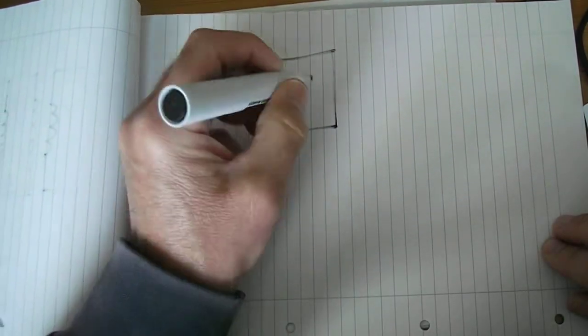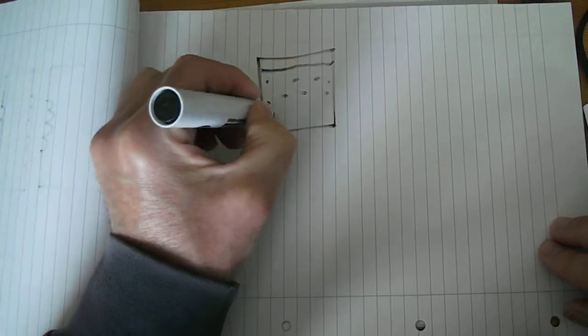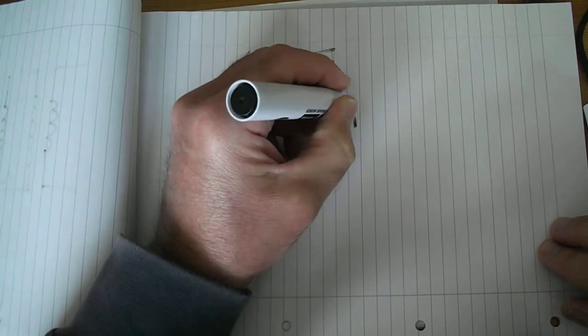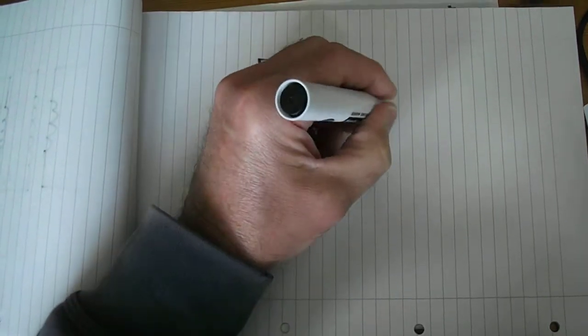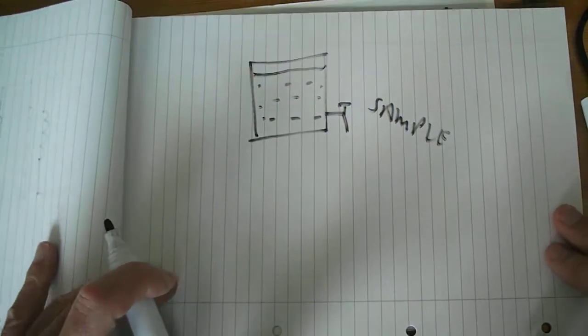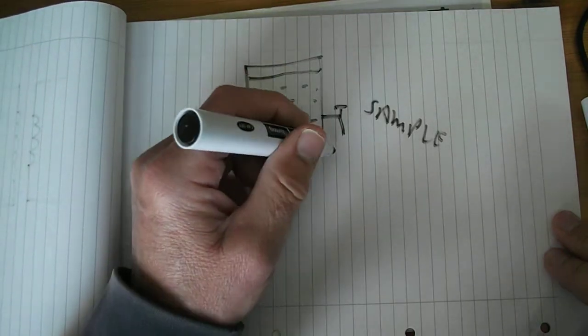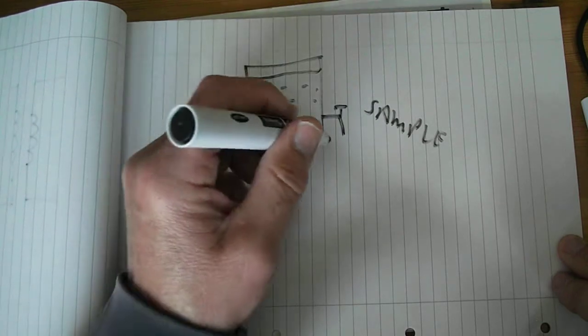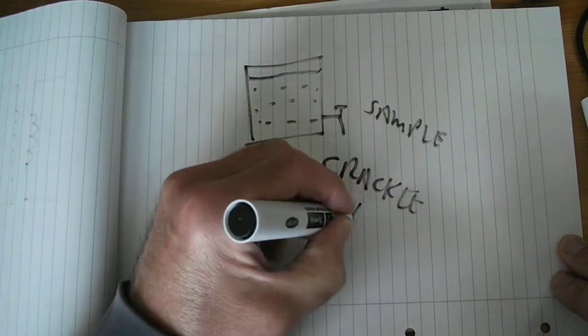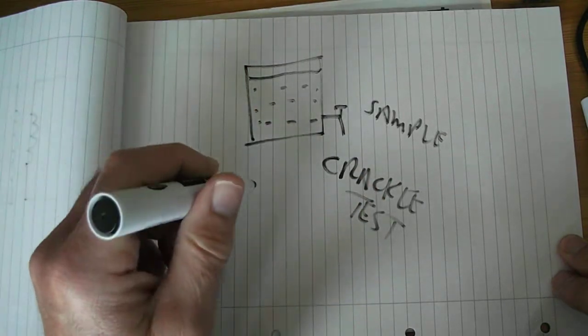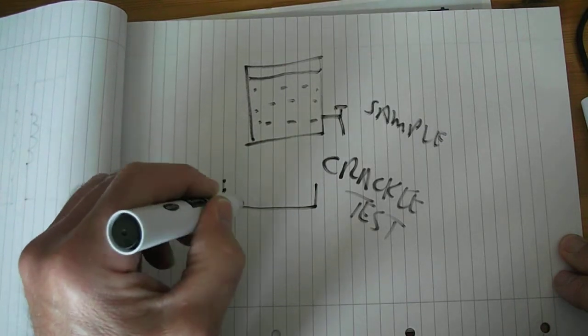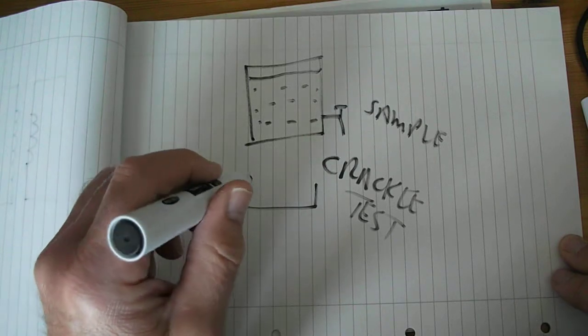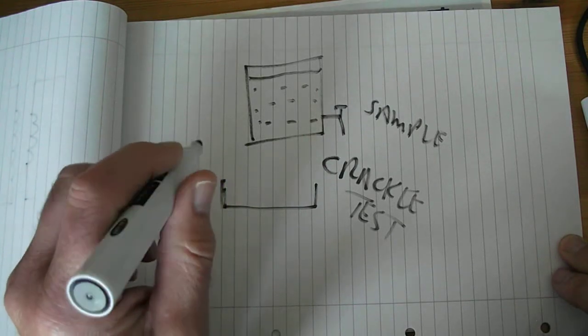What else have we got? The oil in a transformer. There's your transformer, and it's full of oil. There's a tap usually on the outside that you can take a sample, and the test that's used to test the moisture content of the oil is called a crackle test. And the crackle test, what they do effectively is heat up a sample of oil and test whether it spits and crackles to see whether there's any moisture in it.